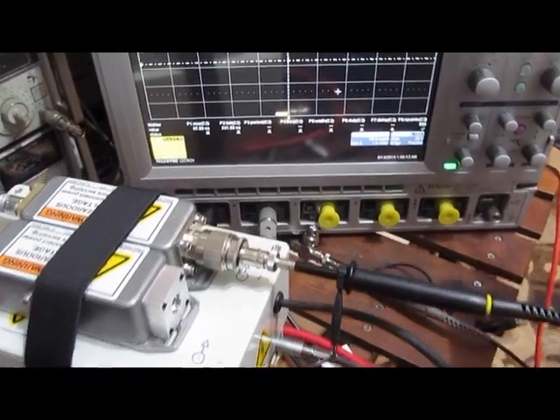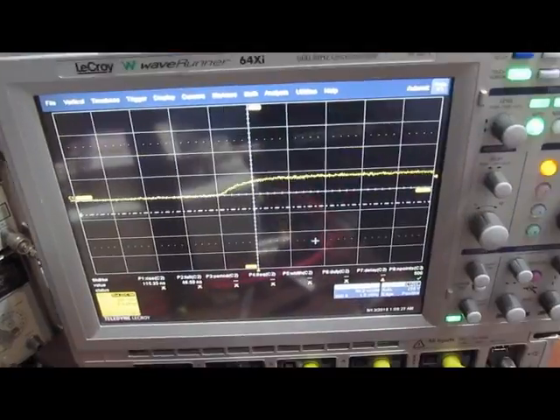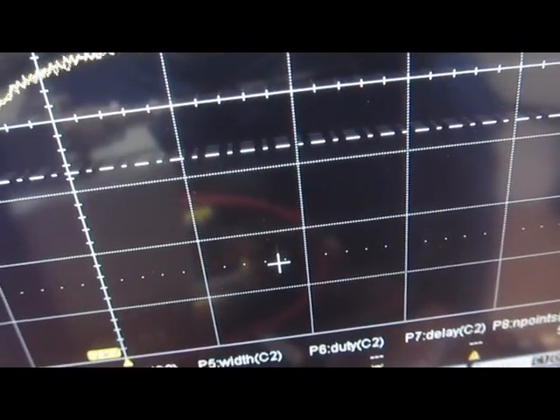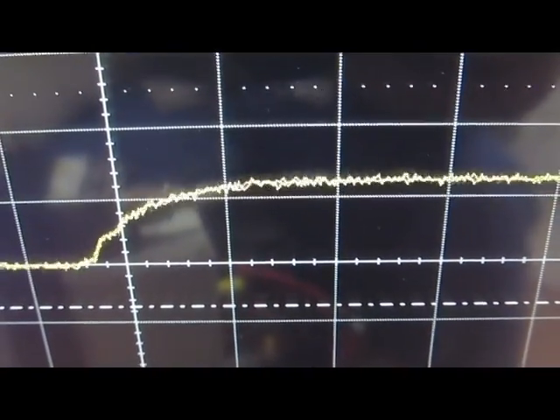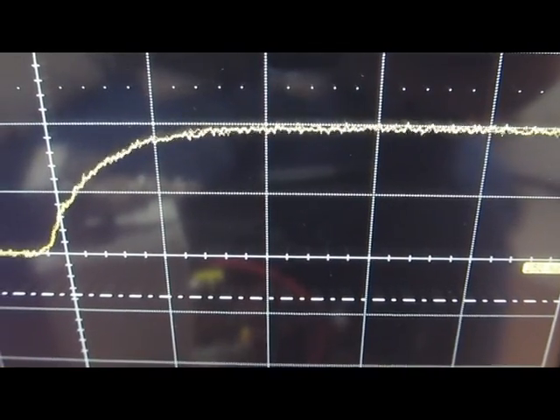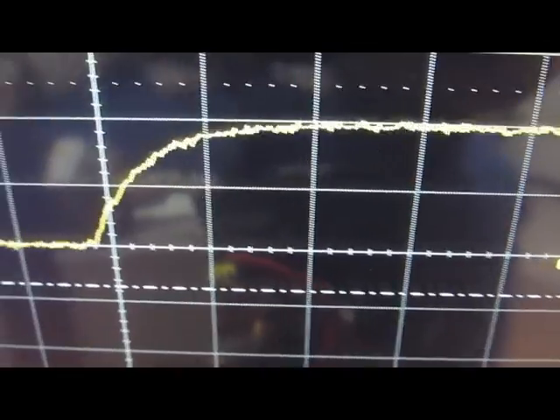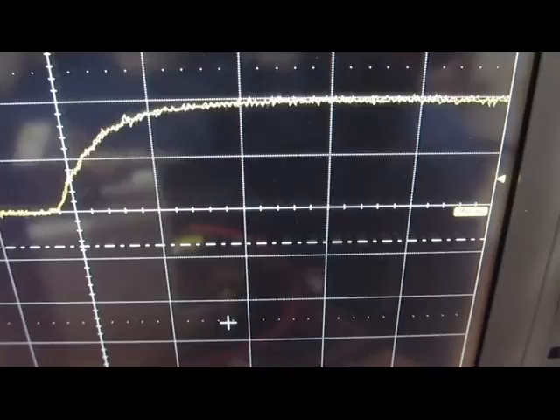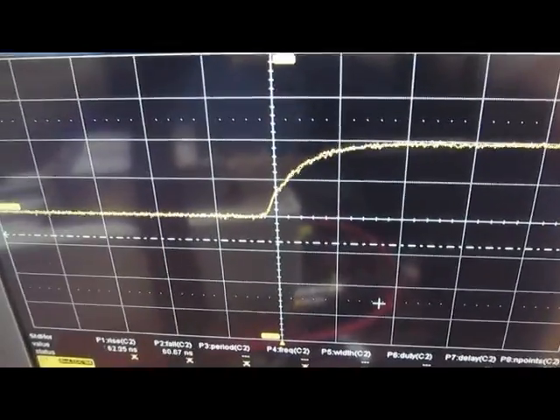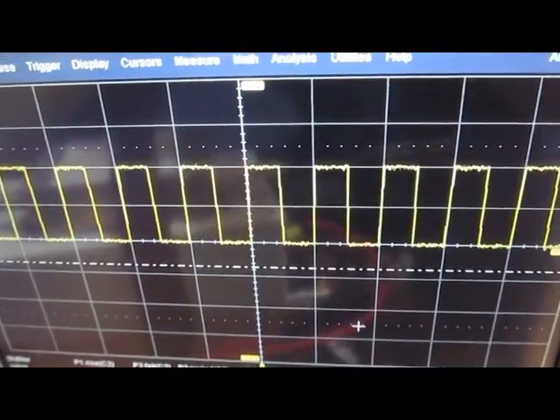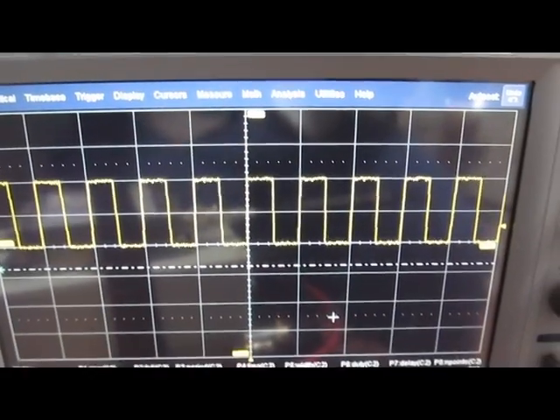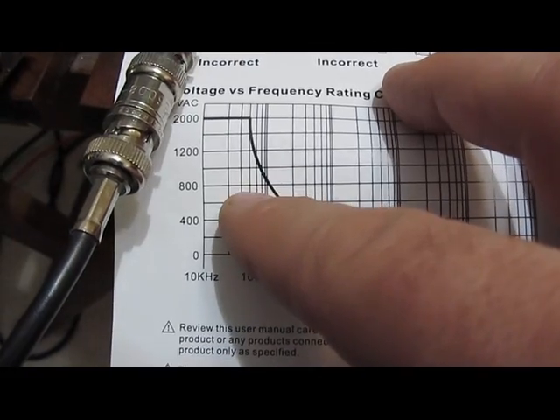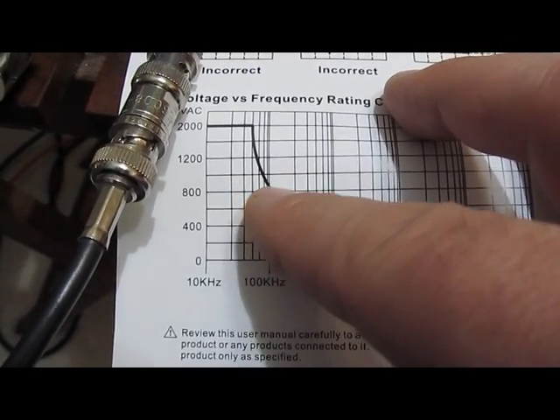Now only the high voltage probe is attached. You can see we're setting it at about 500 volts per division. We're putting out roughly a kilovolt now. The probe doesn't seem to be having too much trouble with this. The previous test I was running up in this area here and I was unable to cause the probe to have any problems.